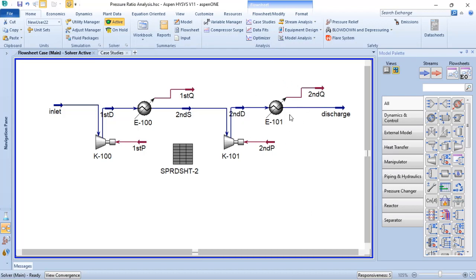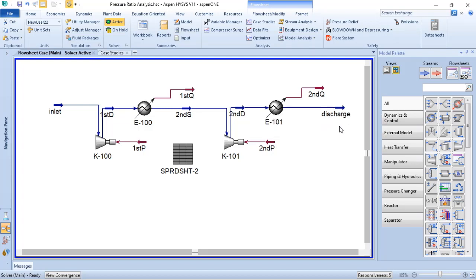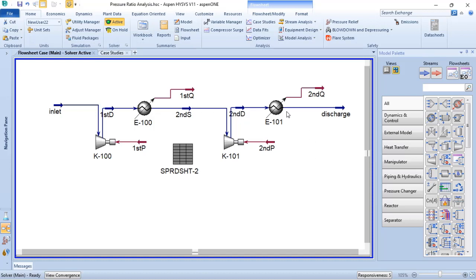The after cooler is needed depending on what will happen with the stream downstream. In this case, the discharge of the second stage of compression is 123°C. If the process needs a hot stream downstream, you would not add an after cooler. But most often, the process must comply with the design temperature, so an after cooler was added here. Heat exchangers between stages of compression are known as intercoolers, and the heat exchanger at the discharge of the last stage is known as the after cooler.